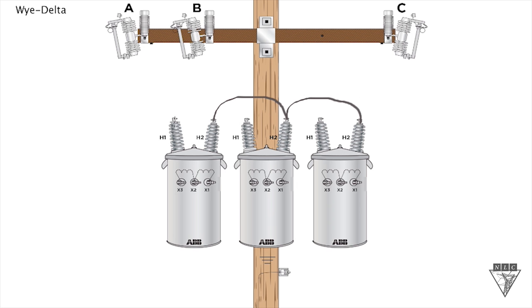Now each H1 bushing is just going to go up to a phase. Take this H1 over to C phase. So we've got our H1's going to each phase, A, B, and C phase, and our H2's are connected together but not to ground. That's our primary Y connection.